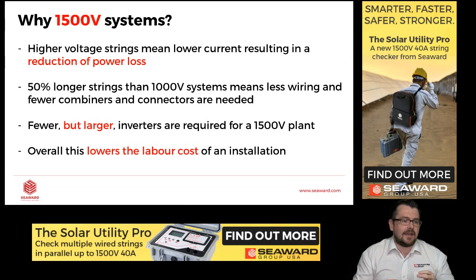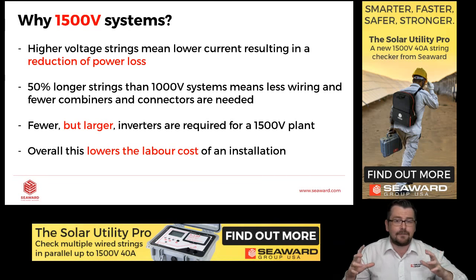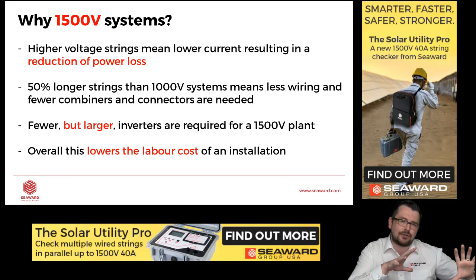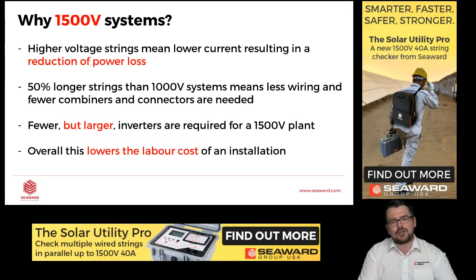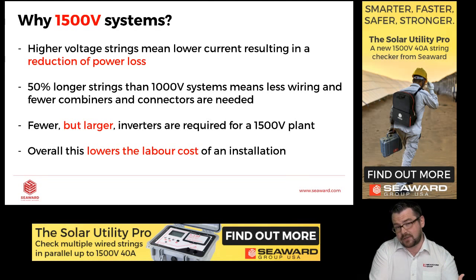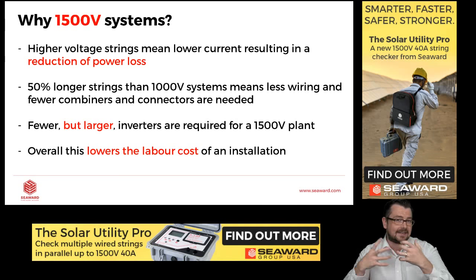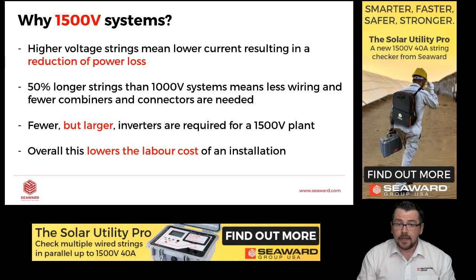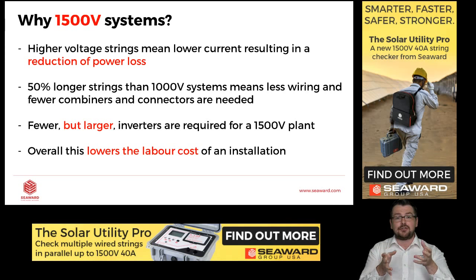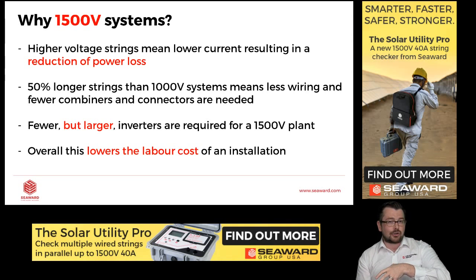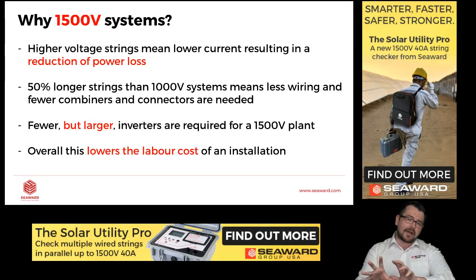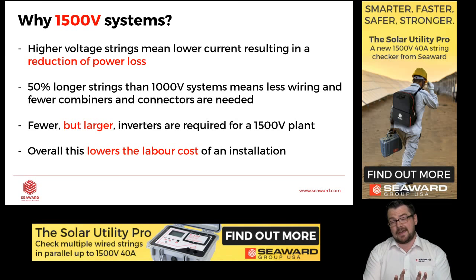And if we have fewer but larger inverters, that means we're also going to save money because the components of the inverters are housed within a similar space as the 1000V systems. So again, we're saving cash not only on the connections and the wiring, the combiner boxes, but also at the DC to AC inverter end. And overall, if we have less materials on site to install, this also lowers the labor cost. So we can put in more solar quicker, or we can put in the same amount of solar for a lower cost. So really, the industry moving to 1500V is a very good thing.